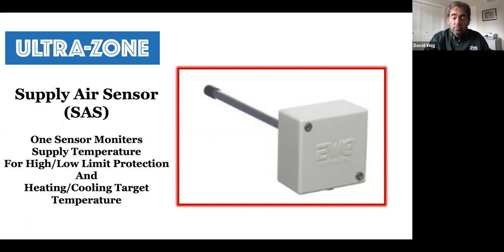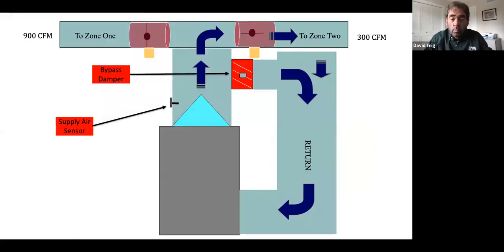So I must install that supply air sensor. Where do I put it? I put it in the main flow. I put it close to the last item in that chain of heating cooling products. So this needs to be after the last heating product, and it needs to be after the last cooling product, so that it can properly read the temperature in both heat mode and cool mode.